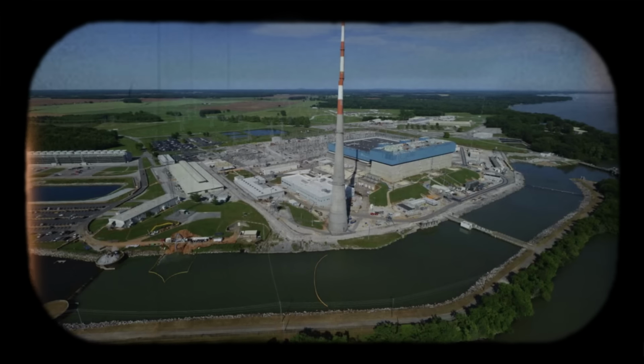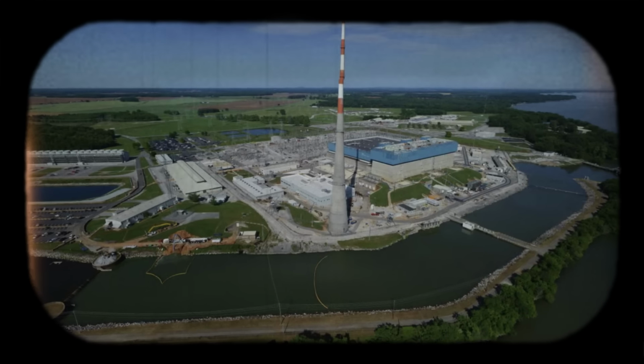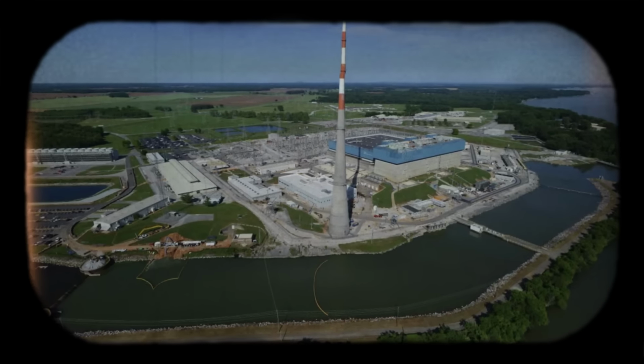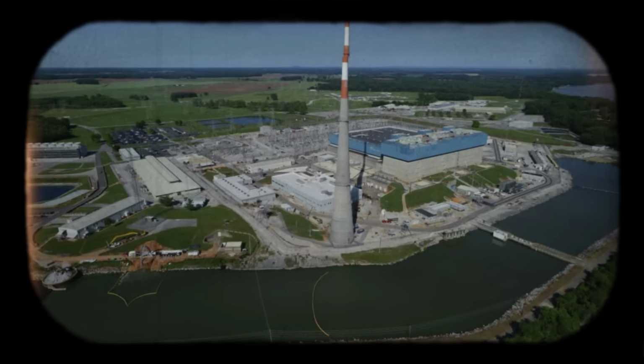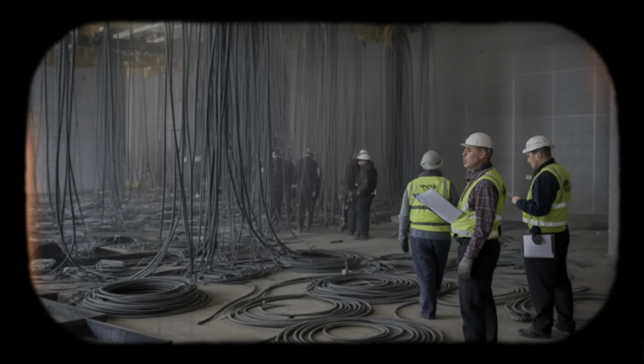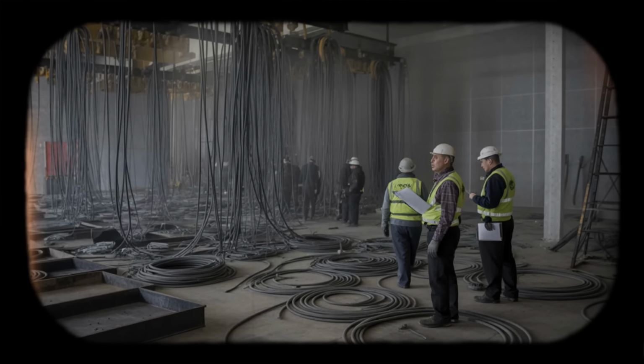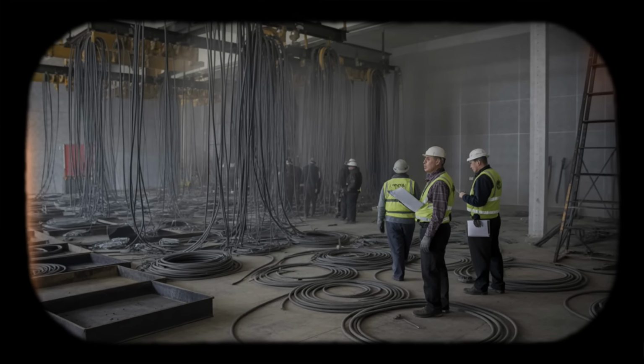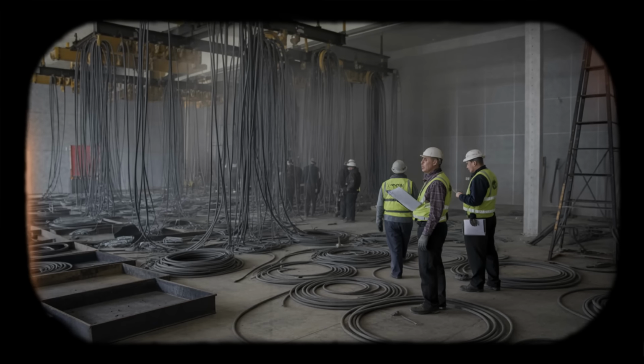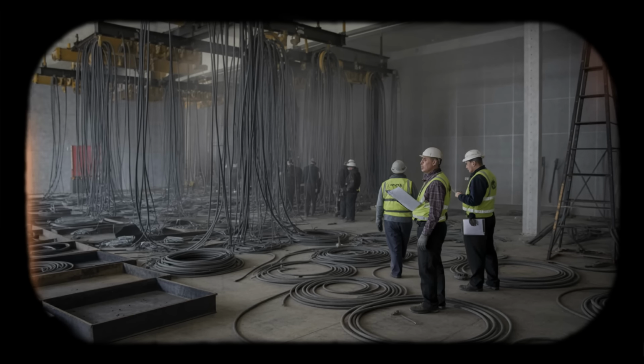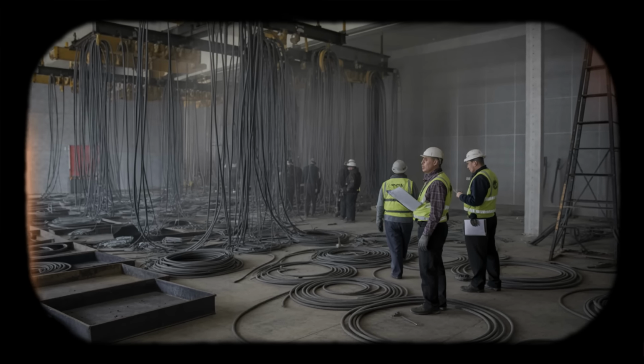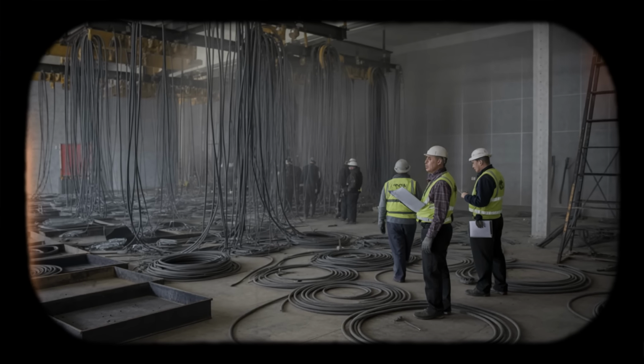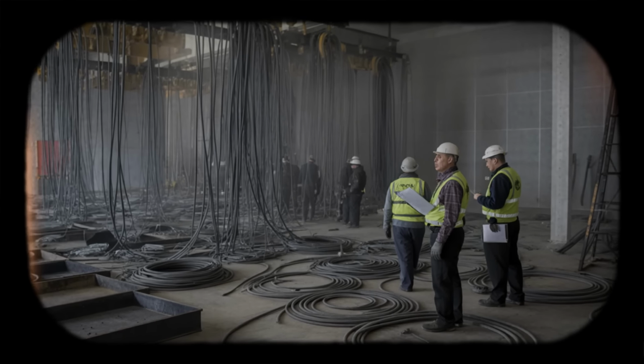The cable spreading room contains thousands of conductors. Identifying which ones burned, which ones were heat damaged but might still function, and which ones are intact requires methodical inspection. Final counts show 1,600 cables impaired to some degree. Of these, 200 control circuits require complete replacement. Complete replacement means pulling new cable through conduits, rerouting through trays, terminating connections at both ends, and testing for proper function. The work will take months, but replacement alone is not sufficient.